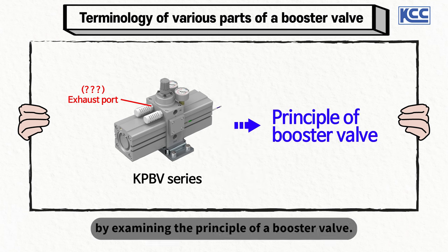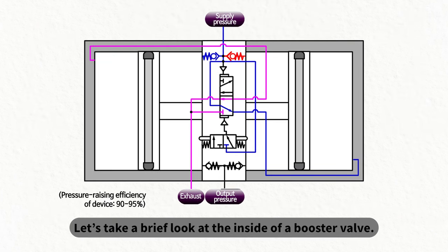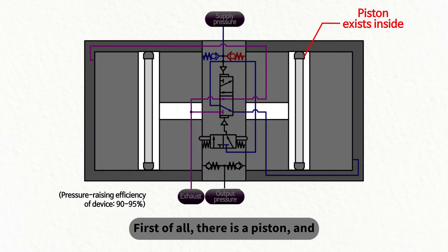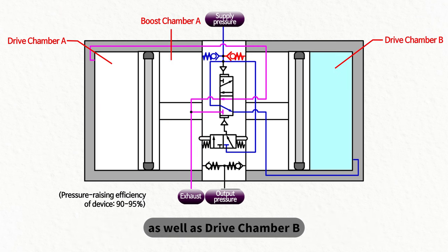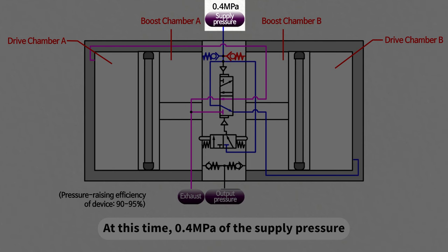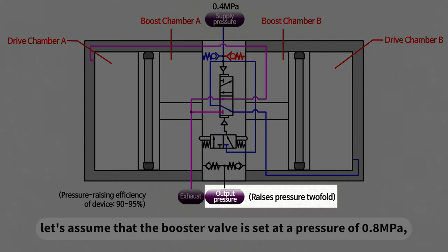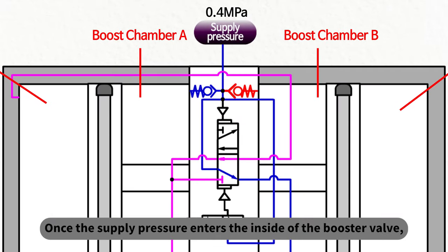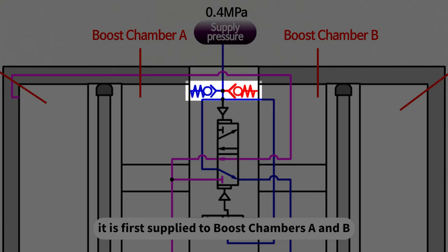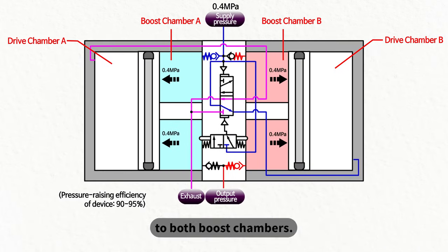Let's study this in more detail by examining the principle of a booster valve using a simple circuit diagram. Inside a booster valve there is a piston, and to the left side of this piston are drive chamber A and boost chamber A, as well as drive chamber B and boost chamber B on the other side. Here, 0.4 MPa of supply pressure is inserted into the booster valve, and the booster valve is set at a pressure of 0.8 MPa — twice the supply pressure. Once the supply pressure enters, it is first supplied to boost chambers A and B through a check valve, and 0.4 MPa of pressure is identically applied to both boost chambers.